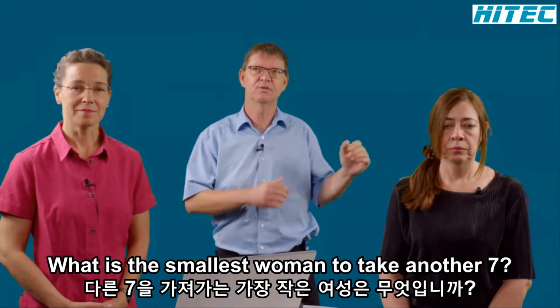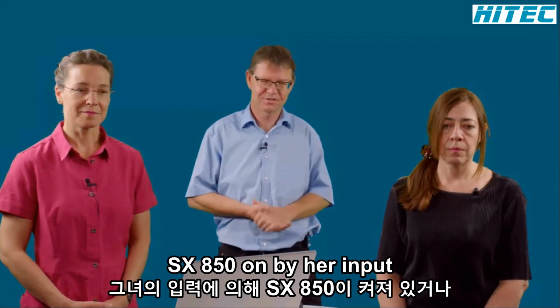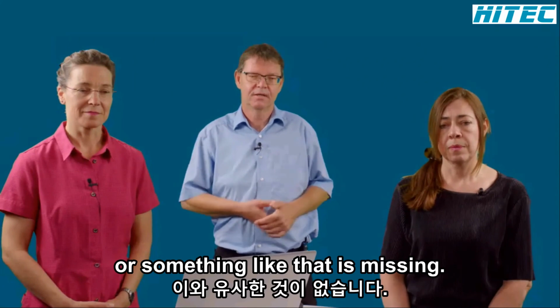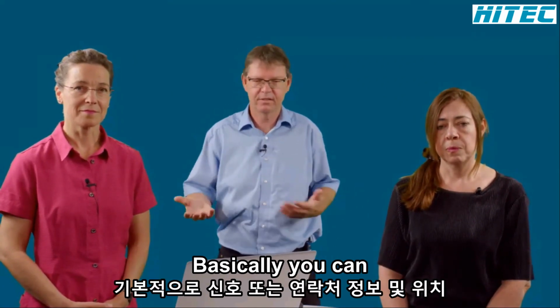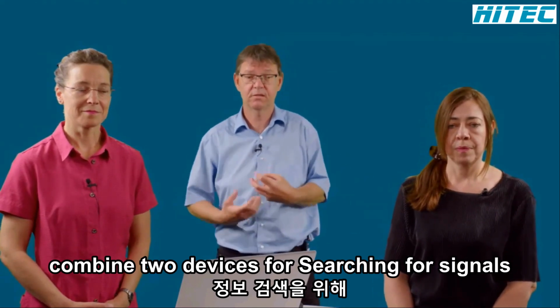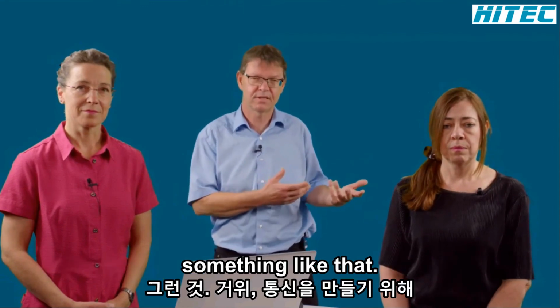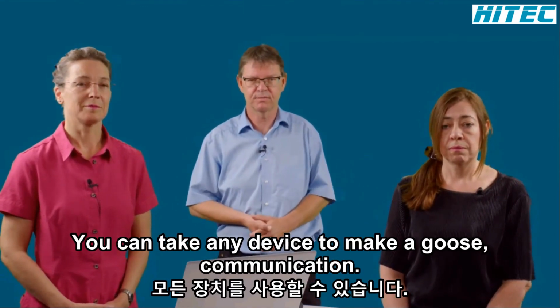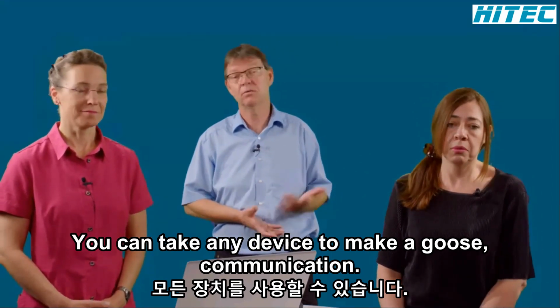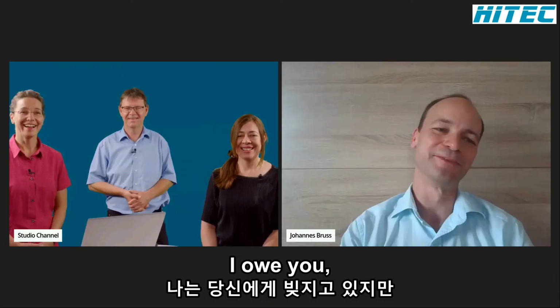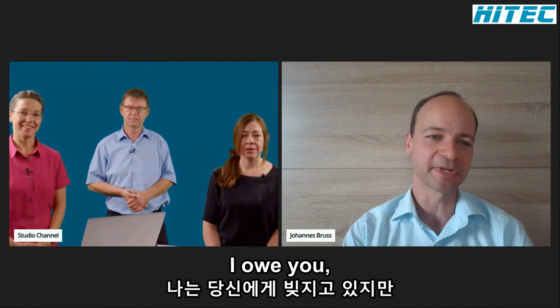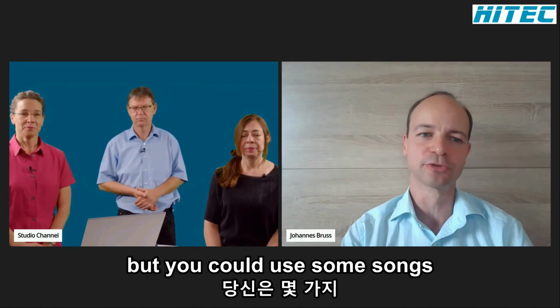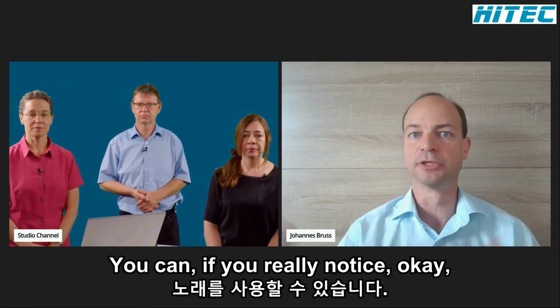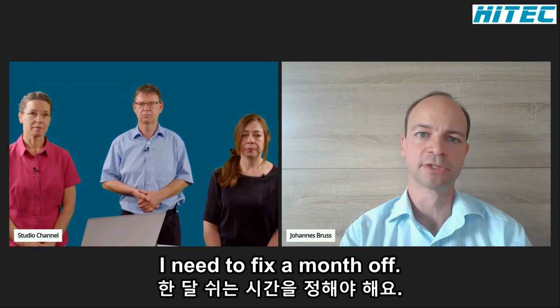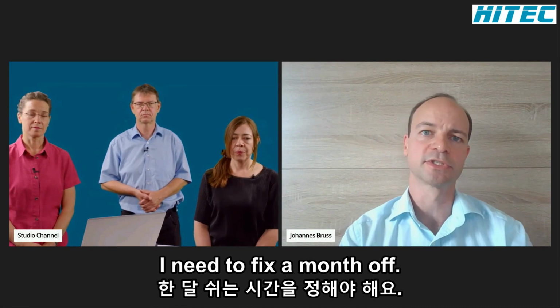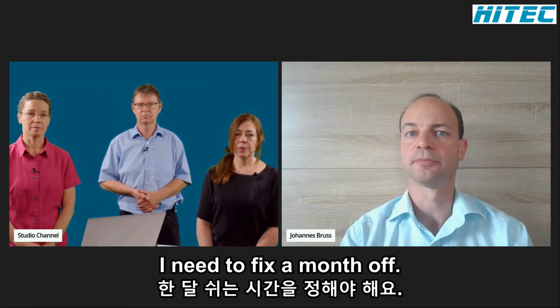So a 7SJ81 maybe is the smallest one. Or you take another 7SX800 if just one binary input or something like that is missing. Then this is maybe the smallest hardware variant. But basically, you can combine the devices for getting GOOSE signals or contact information or position information. You can take any device to make the GOOSE communication. Actually, a SICAM A8000 would also be an option. And let me also step in. What we could also offer is the SICAM I/O unit. If you notice you need additional I/Os, you can use the SICAM I/O unit and connect it via GOOSE communication to the 7SX800 to extend the amount of inputs and outputs.